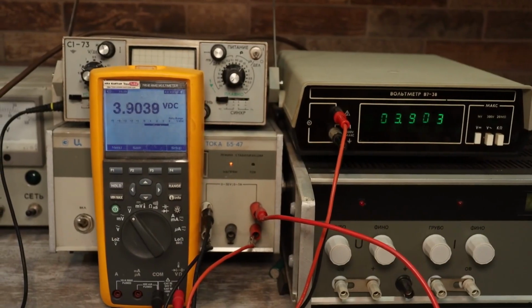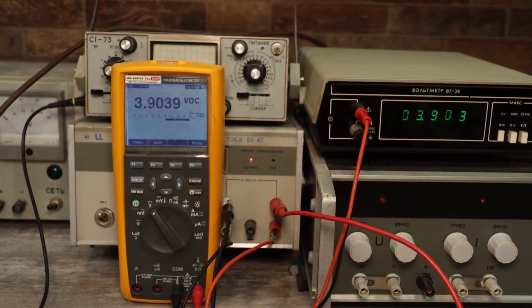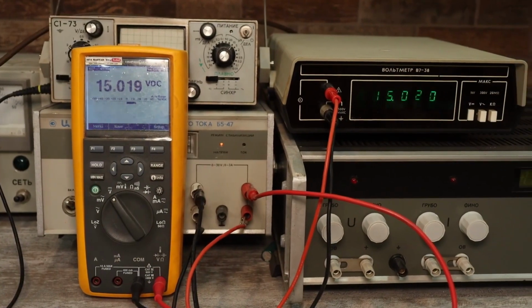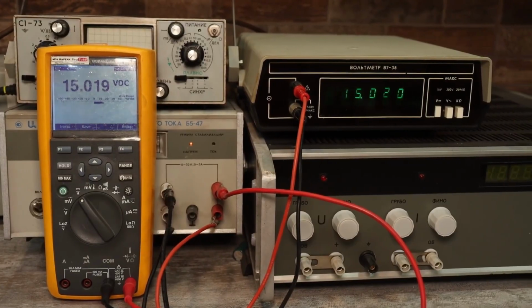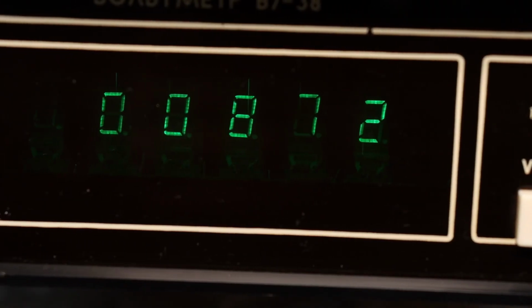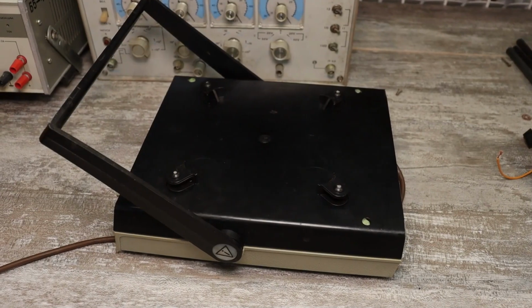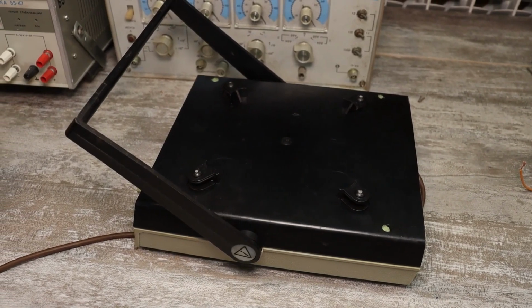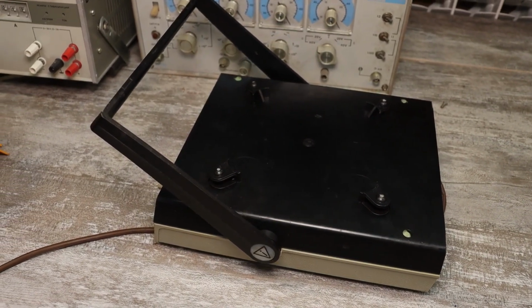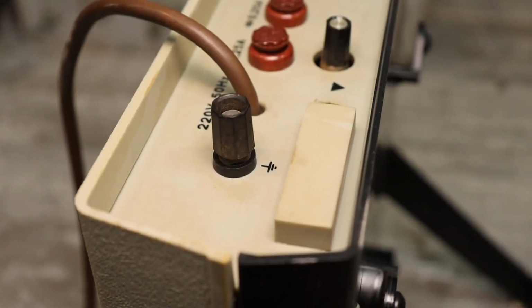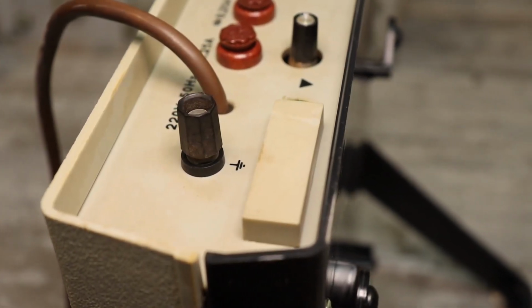The main characteristics are as follows: DC and AC voltage from 10 microvolts to 1000 volts. The average error for DC voltage is 0.04 to 0.07. In the case of AC, based on frequency, the average error ranges from 0.4 to 1.5.